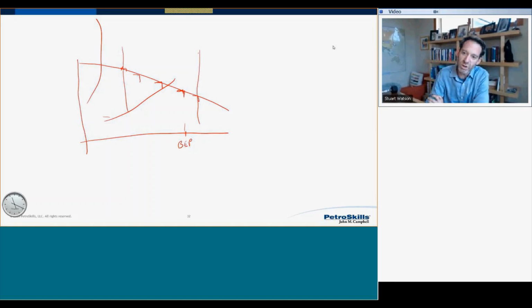And then the second part, you start talking about suction velocity. There is a term that we haven't talked about in this webinar here: suction-specific speed. Suction-specific speed starts to get into the suction energy requirements at the inlet eye of the pump, and this starts to tie back to this suction velocity idea. There are some very interesting papers. As your suction-specific speed, in foot-pound-second units, approaches 10,000 to 11,000, we talk about suction stability and needing to either reduce RPM or increase the net positive suction head available. That might be some guideline that helps with that.